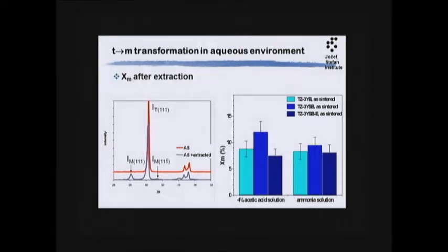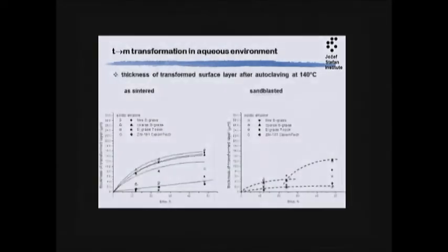The old results: in extraction, we saw phase changes on the surface, but at that time, that method, which was the only one in the standard, we were not able to resolve any difference between the materials. But when we did longer autoclaving, then we saw the big difference between the standard grade materials and the biomedical grade from Tosoh, and we checked at the same time.